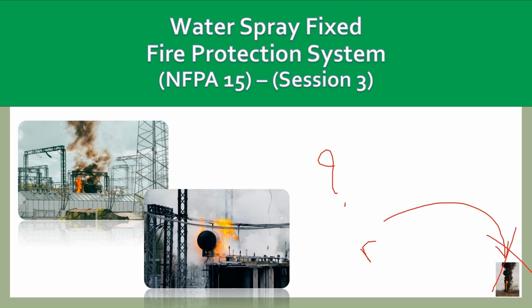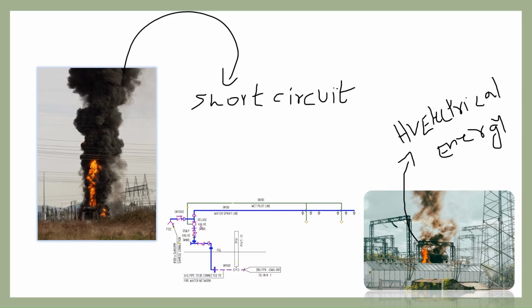So in this video, we are going to explore the design concepts of water spray fixed fire protection system that can prevent disaster in high risk areas like factories, power plants and substations. So let us imagine a particular scenario of a substation, and we already know that cables and cable trays will be installed in a substation, and the cables carry high voltage electrical energy and they are coated with highly combustible materials. So a short circuit in a substation triggers a fire in the cable trays. So the fire quickly spreads, risking catastrophic damage.